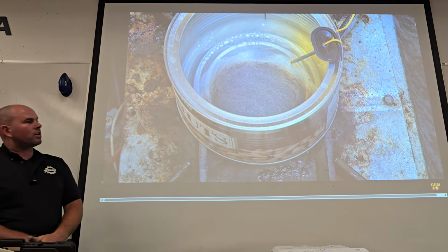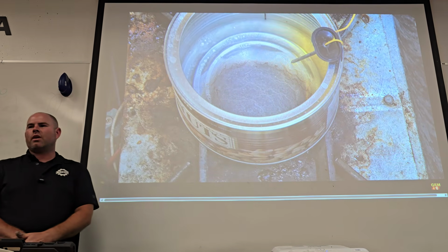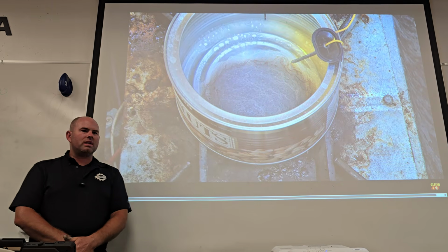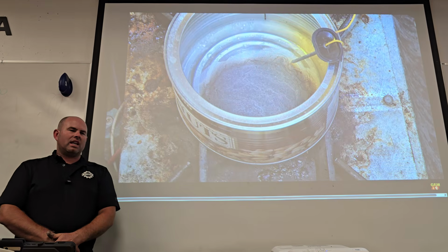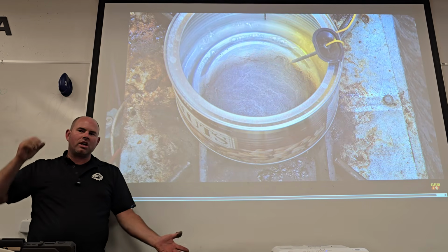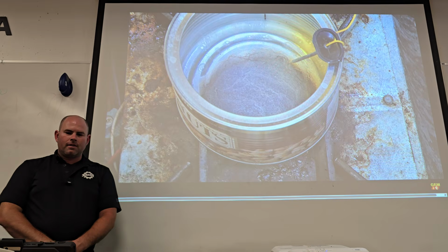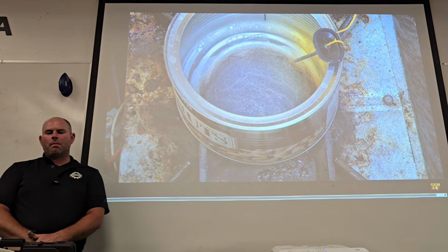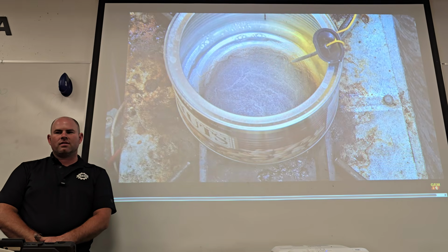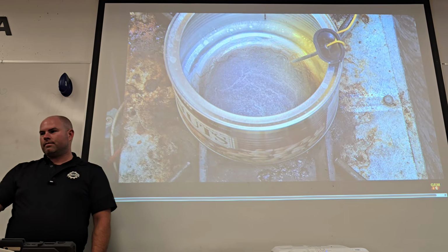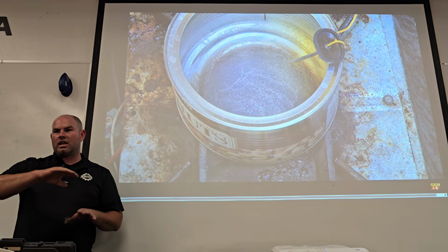But where the water's at, look, it's not because the water's cool. It's because the water is absorbing all those BTUs and it's not becoming sensible heat. It's all as latent heat. They'll call it invisible heat sometimes. Cool, so now you go, there's just a little bit of water left. What do you think is going to happen as the water goes away? The can's gonna get hot. Exactly, it goes back to sensible, and then you're going to actually start to see it getting hotter and hotter and hotter, right?